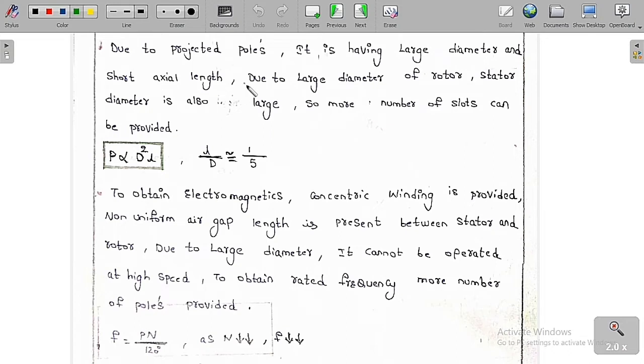Power is directly proportional to diameter square into length L, the short axial length, where D is the diameter of the rotor and L is the short axial length. D is always greater than L. If you take the ratio of L by D, it is nearly equal to 1 by 5, or we can say diameter is nearly equal to 5 times the short axial length. Power output is directly proportional to square of the diameter and the length; if these are high, power is also higher.